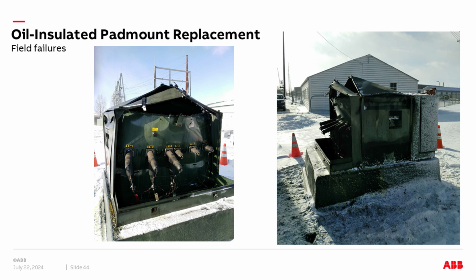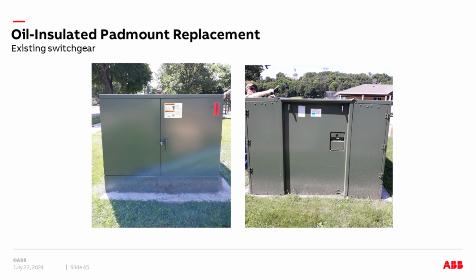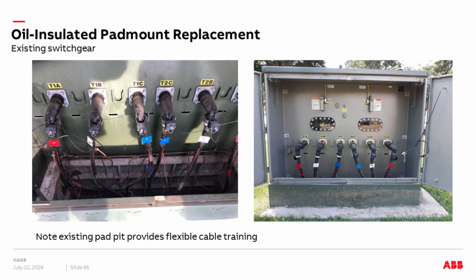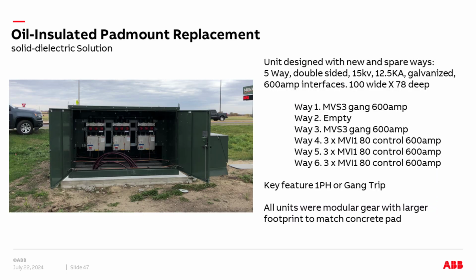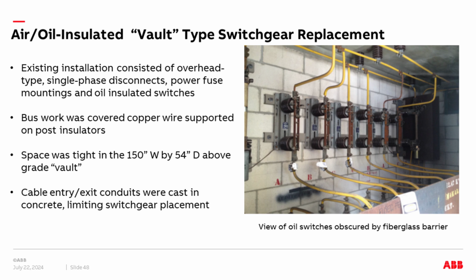Another utility did have an issue where old gear failed and had to be replaced. This was excessive moisture in the oil, and the gear failed violently. And then the new gear matching the pad exactly, and you can see the existing cables are coming out of a pit. So there's quite a bit of flexibility for moving them over and up and down a little bit. You don't have to be as rigid about the locations. And when the replacement unit came in, you can see in this case, it's 5-way double-sided. There's an empty way on the other side. On this side you can see 3 ways, and on the other side there's space for future.